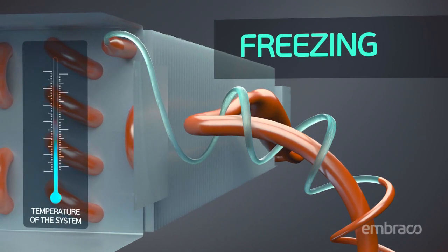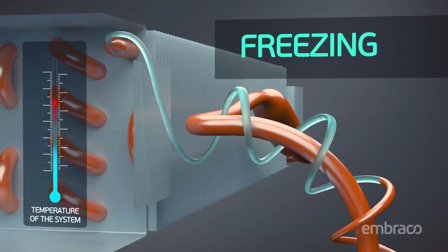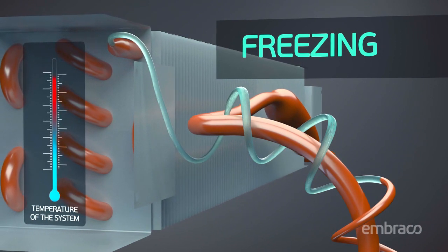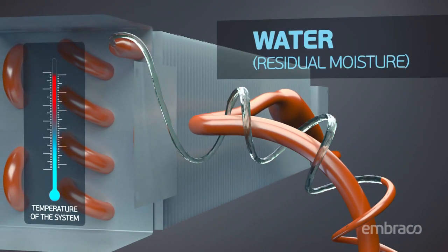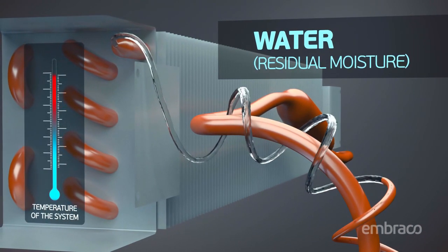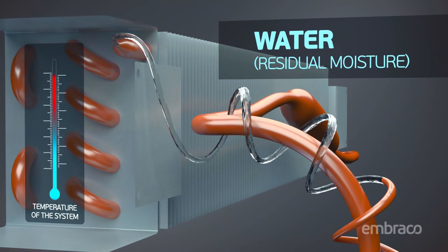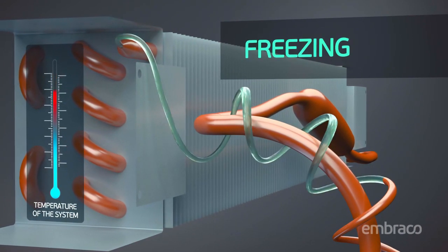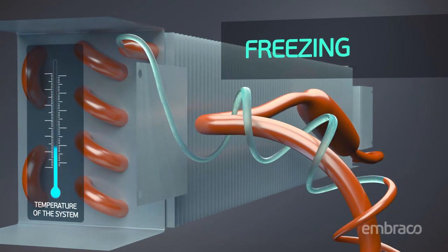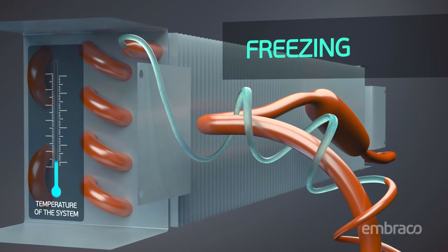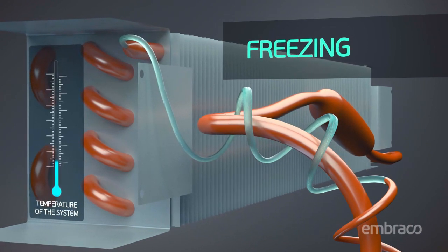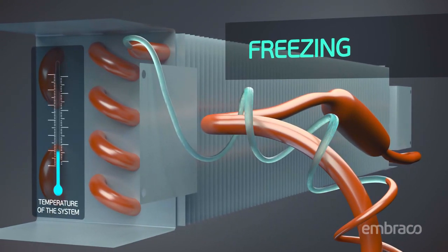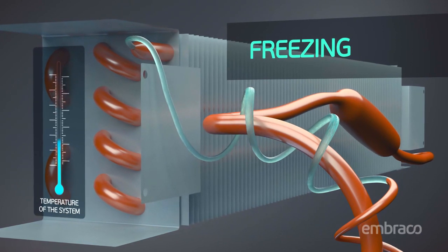By unplugging the refrigerator, the ice that was blocking the capillary will melt and cause the refrigerator to operate again. However, when it starts working again, the capillary will freeze once more, generating an intermittent blocking and unblocking cycle of the capillary, which can compromise food quality and preservation.